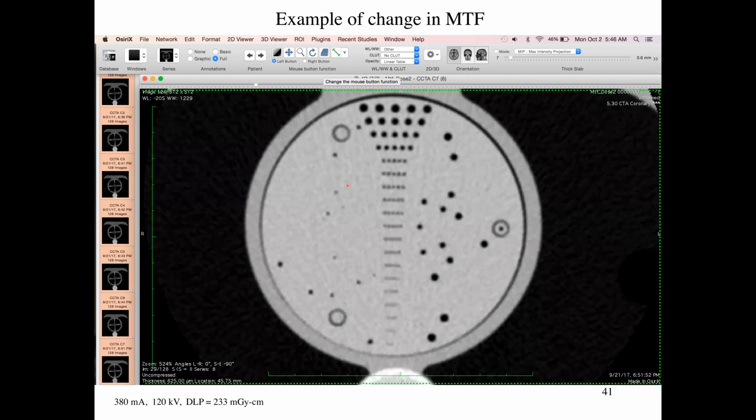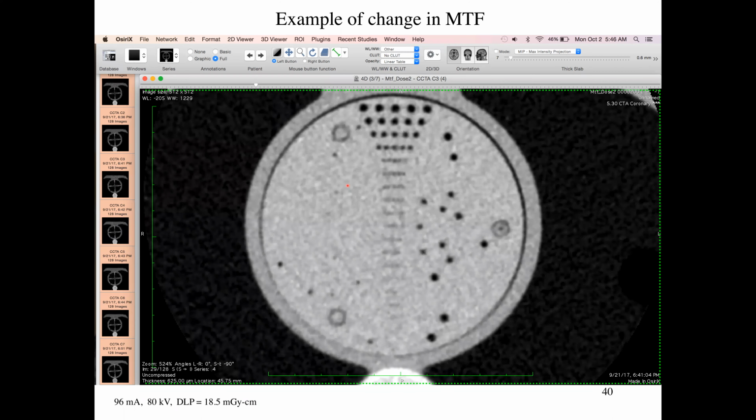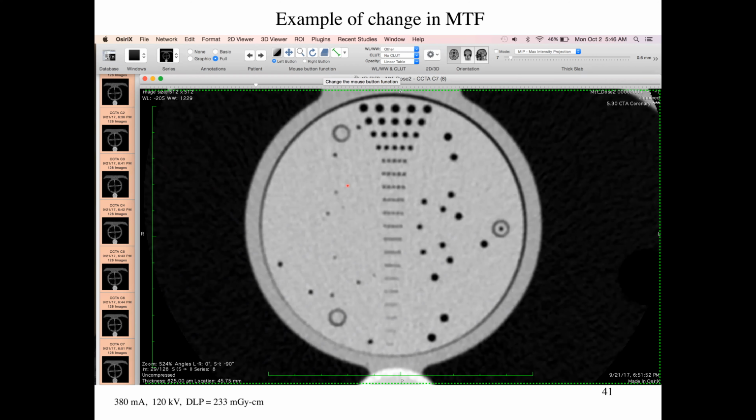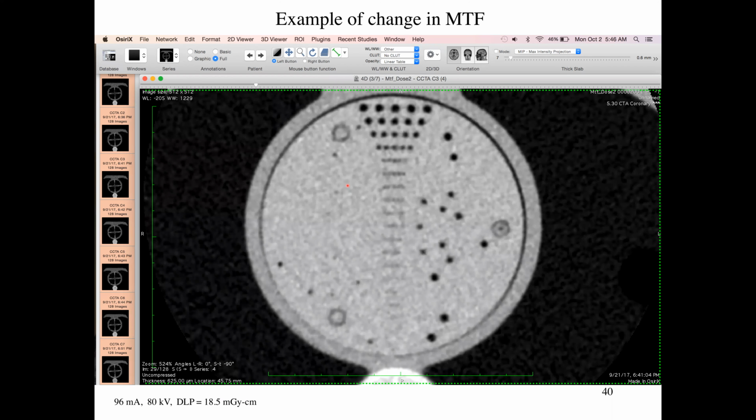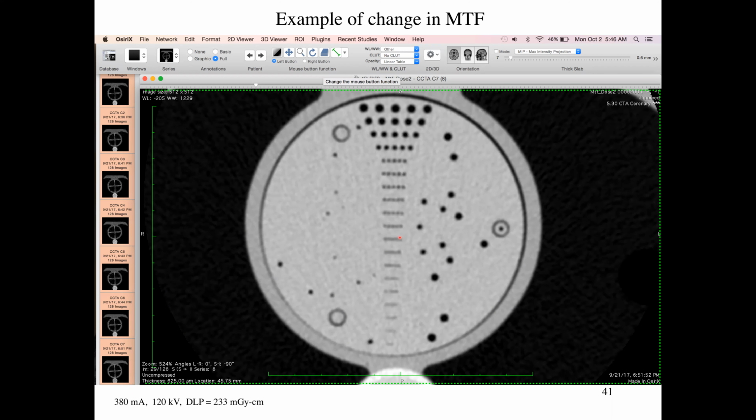And then compare it with that picture. So I'm going to flip back and forth. Okay, so 300 mA, versus say 100 mA, so that's basically 4 times more radiation than that. So if our job requires us to detect how many holes are right here, this won't do the trick, right? We can't see it, right? This one, we can see probably that. And the reason that this quality gets better is just you have higher counts on your detector.